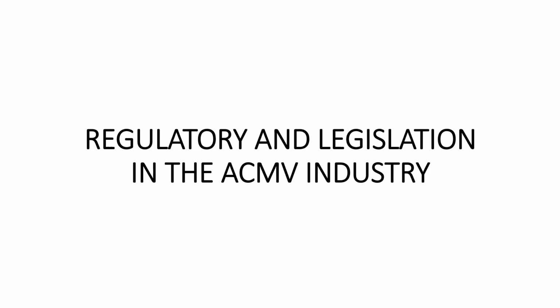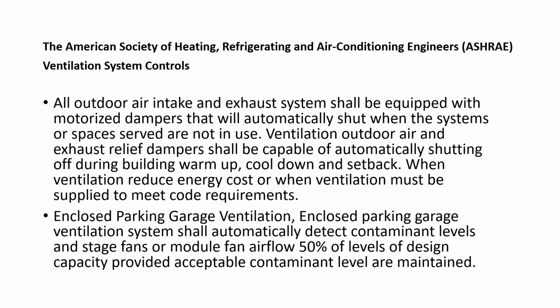Regulatory and legislation in the ACMV industry. The American Society of Heating, Refrigerating and Air Conditioning Engineers stated that all outdoor air intake and exhaust systems shall be equipped with motorized dampers that will automatically shut when the system or spaces served are not in use. Ventilation outdoor air and exhaust relief dampers shall be capable of automatically shutting off during building warm-up, cool-down and setback, when ventilation reduces energy costs or when ventilation must be supplied to meet code requirements. Enclosed parking garage ventilation systems shall automatically detect contaminant levels and stage fans or modulate fan airflow to 50% of design capacity, provided acceptable contaminant levels are maintained.